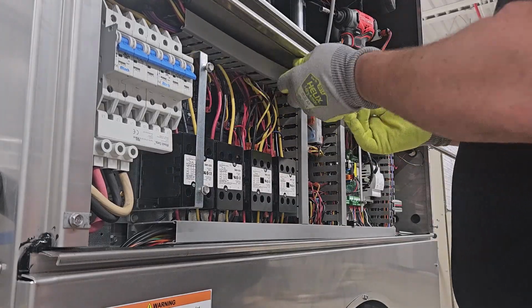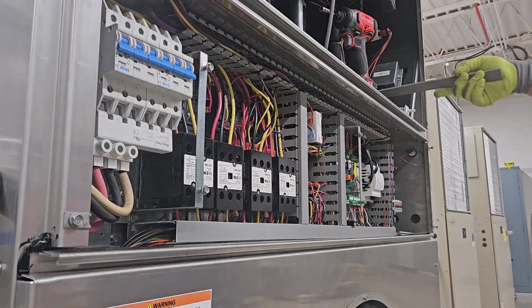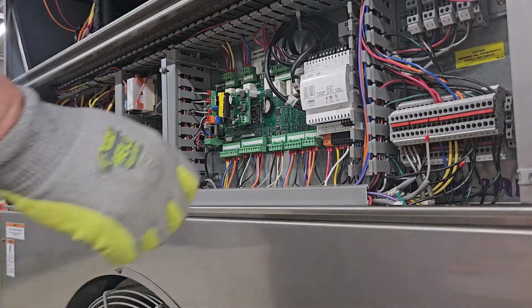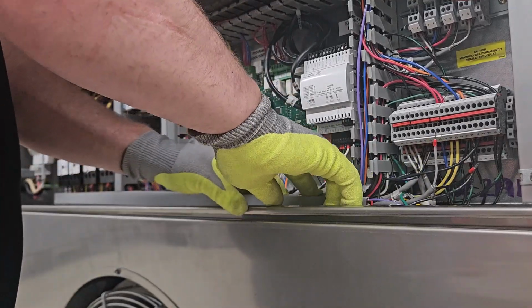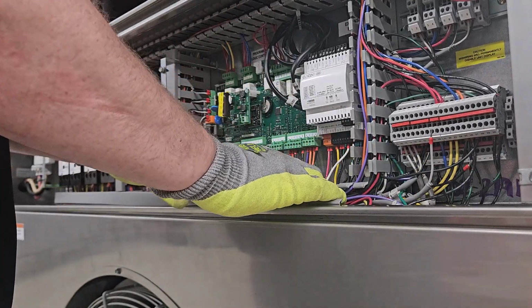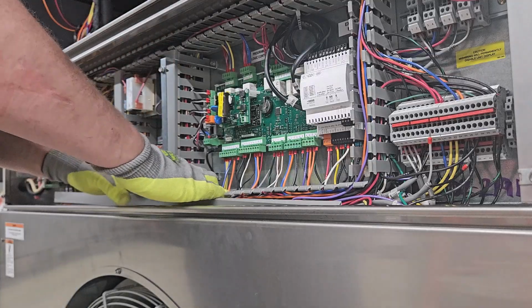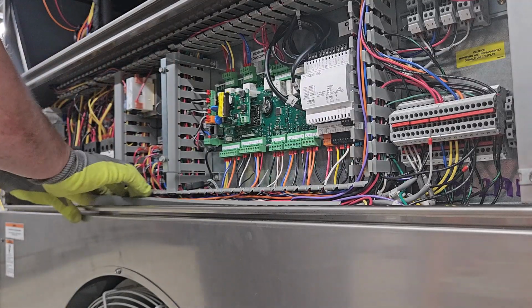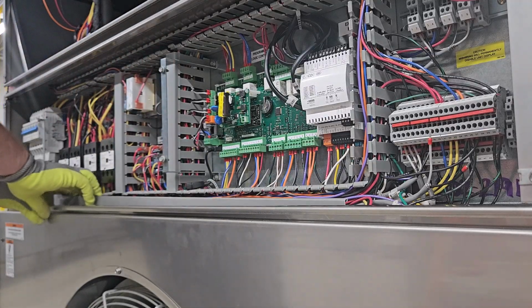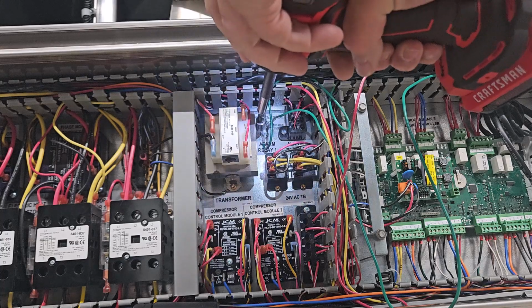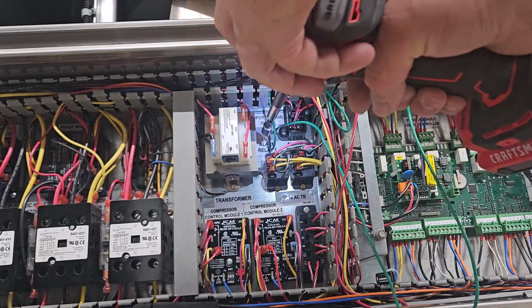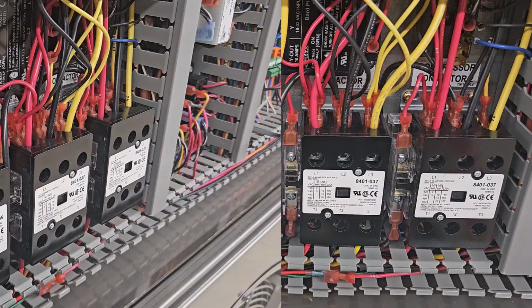Remove the wire chase channel housing the electrical and communication wires for the indoor blower motor. The indoor blower motor is powered all the time with 240 or 460 volt power supply and is controlled using a 2-wire Modbus communication. Remove the grounding screw. This is the ground location for both the evaporator and the condenser fan motor. Remove the high voltage power wires from the line side of the contactor.